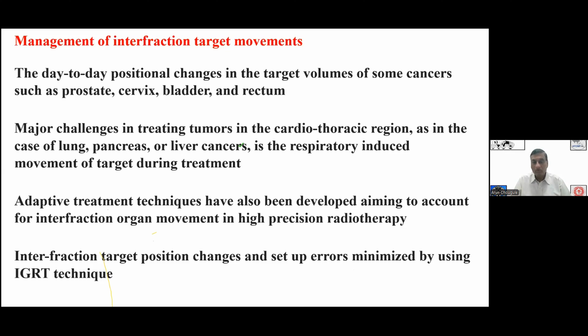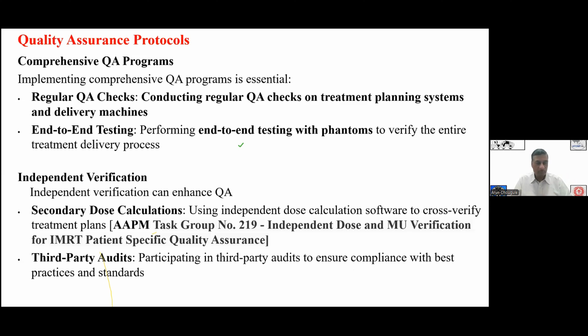So a comprehensive QA program is very, very important. Regular QA checks and end-to-end testing with a phantom, to verify the entire treatment delivery, are very, very important. So it is a lot of work for the medical physicist and dosimetrist. Independent verification can enhance QA. So secondary dose calculations, and the plan has to be used. AAPM has given a task group report on independent dose and MU verification for IMRT, the Task Group 219 report. Third party audit, and the IAEA also suggests auditing of this. So accuracy is very, very important.